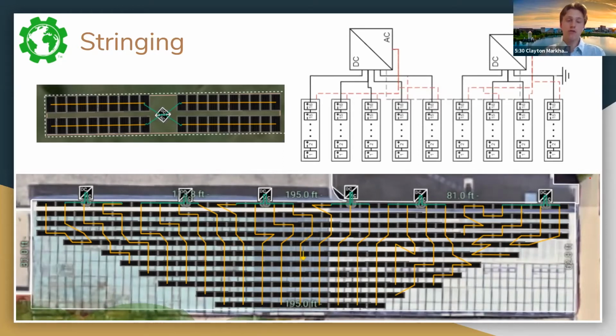These generally show our strategy to combine 10 panels together in series, and then 4 of these strings together in parallel to each inverter to get the most bang for our energy buck from each inverter. In the graphic below, you can see how we strung panels from the bottom up on the architecture building to minimize the length of DC wiring needed and to minimize the number of inverters needed.